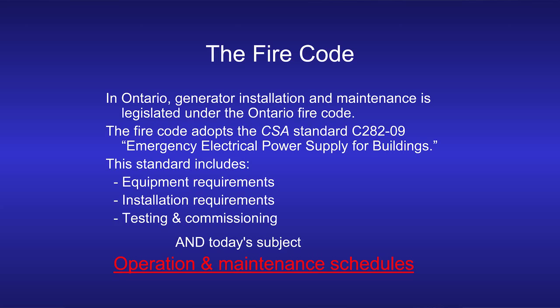The emergency generators are mandated by the building code according to the size and type of occupancy of the building, and the CSA standard that controls how the system is designed and installed is C282. The latest edition of which came out this April, the 2015 edition.